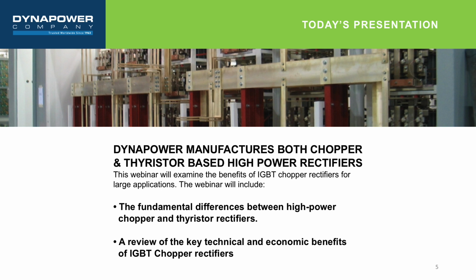Today's presentation will concentrate on the fundamental differences between Thyristor and IGBT chopper rectifiers. Dynapower manufactures both chopper and Thyristor-based high-power rectifiers for large industrial applications worldwide and has successfully been doing so since 1963. There are several key technical considerations for evaluating high-power rectifier topologies that engineers must consider before recommending the optimum rectifier configuration for any project. These include power factor, harmonics, transformer design, ripple, efficiency, as well as space and installation requirements.